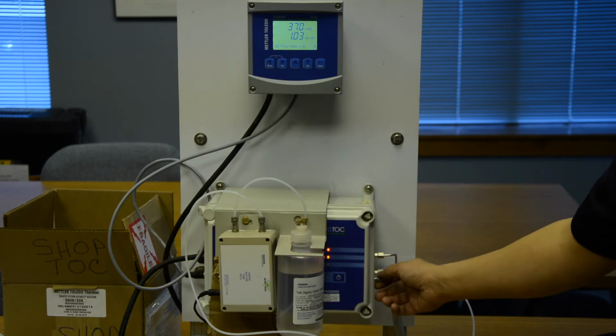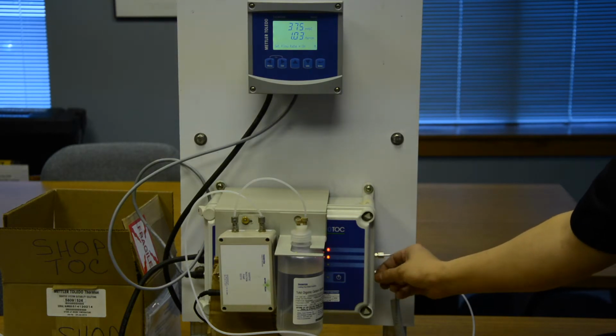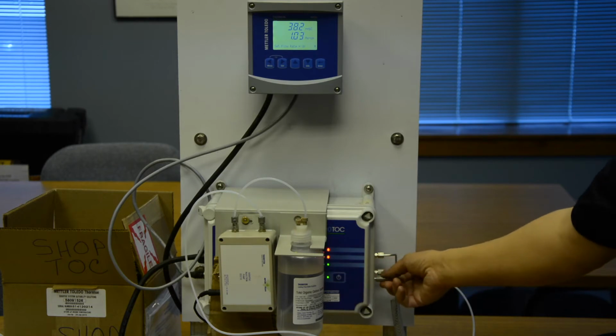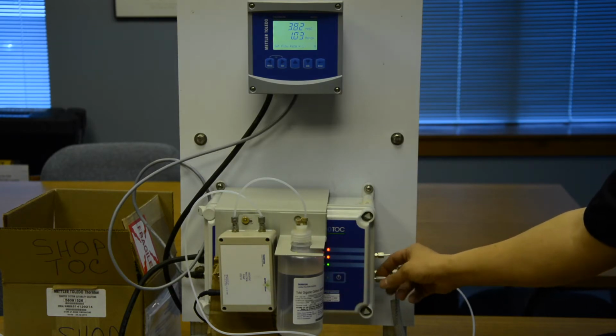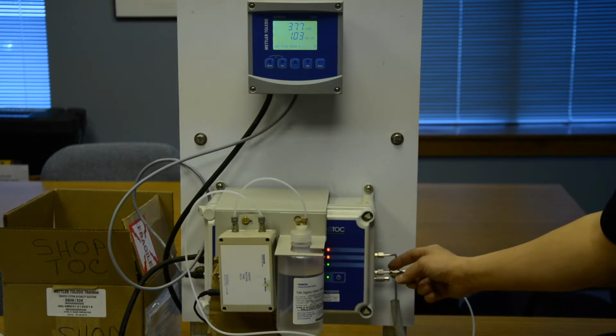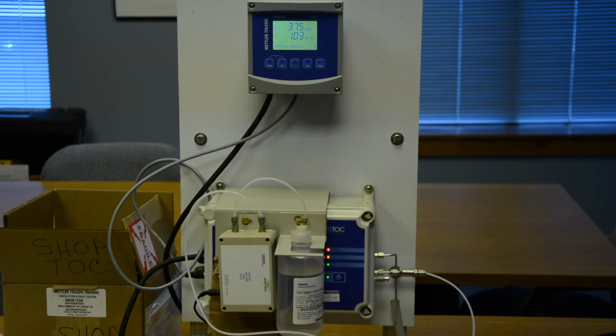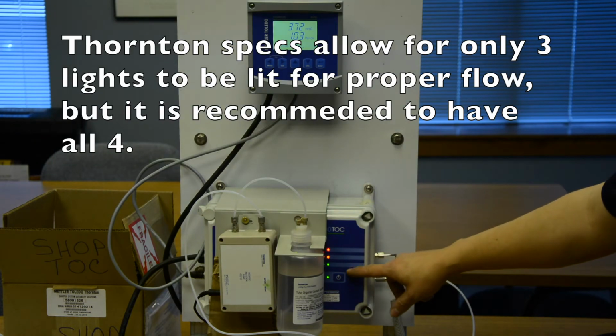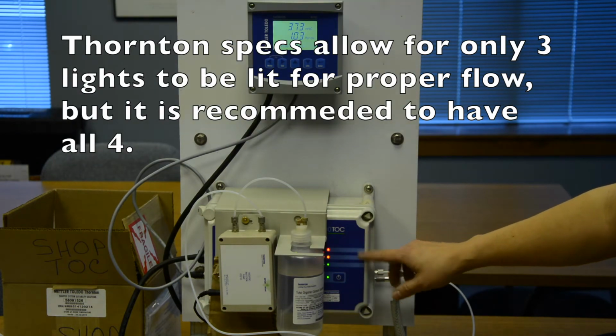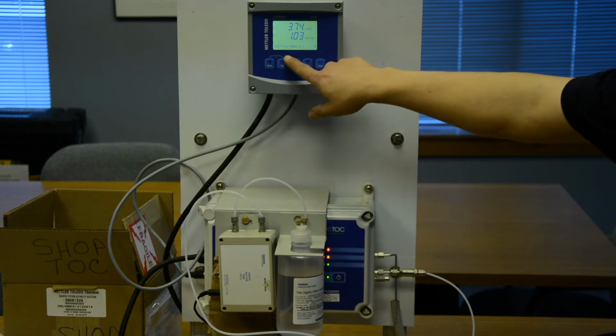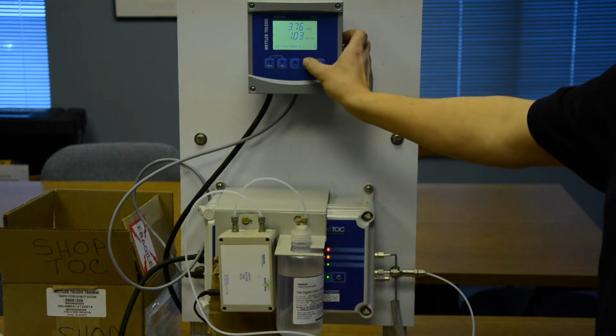Turn clockwise to close your valve down until you get the proper flow where all 4 lights are showing. You may need to play with the unit for a little while to get the flows to level out. Once the flows have stayed at 4 lights that are lit consistently for a couple seconds, go back into your set flow rate and change it back to off.